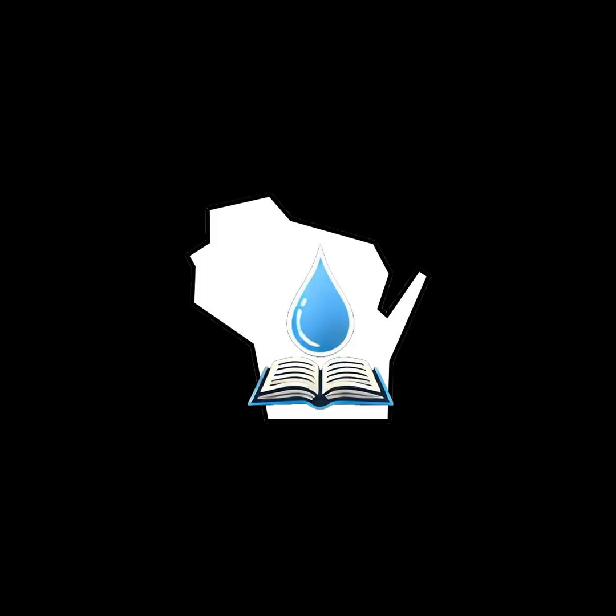Now let's layer in another common question. How do you size a local waste line serving a T&P relief valve? Well, the answer is you size the local waste based on the receptor's DFU value. You don't size it off the T&P pipe directly. You go to Table 1 in 382.30 and use the receptor's drainage fixture unit value to pick the right size pipe. This is a subtle point, but one that's really important when designing discharge piping for safety valves or multiple pieces of equipment dumping into a single receptor.